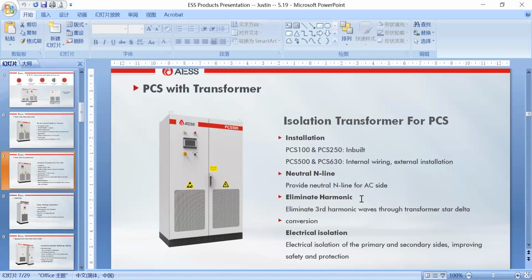Why do we need the isolation transformer? Three reasons. First, we need the neutral line for the AC side, because normally the inverter in the PCS only has three phases: phase A, phase B, and phase C. But since we're working on commercial and industrial big projects, we need the neutral line for the AC side.